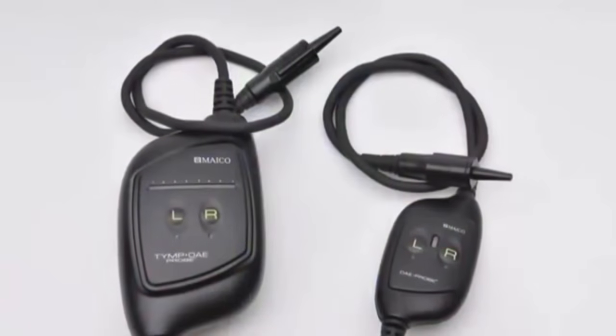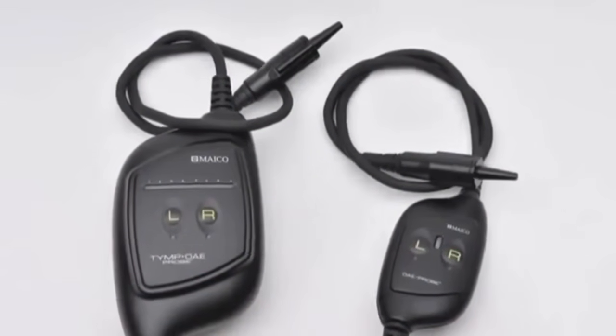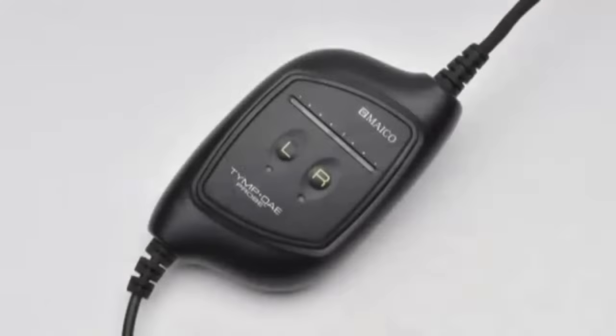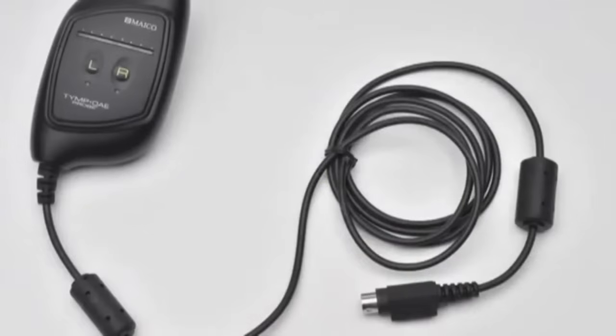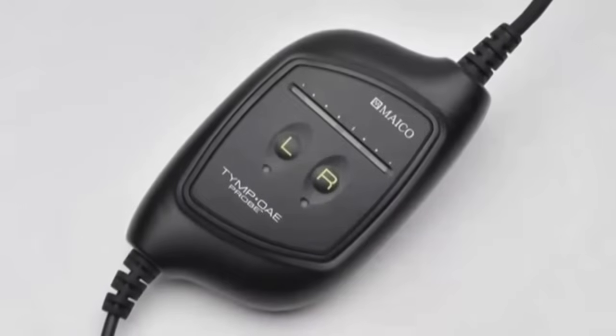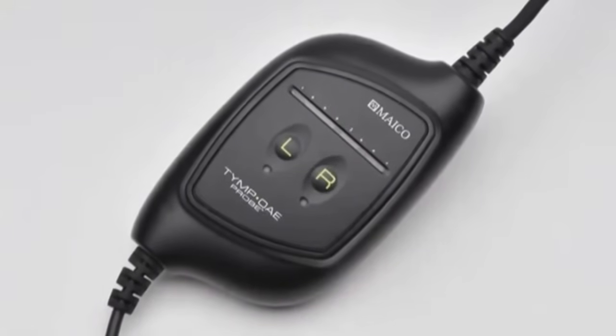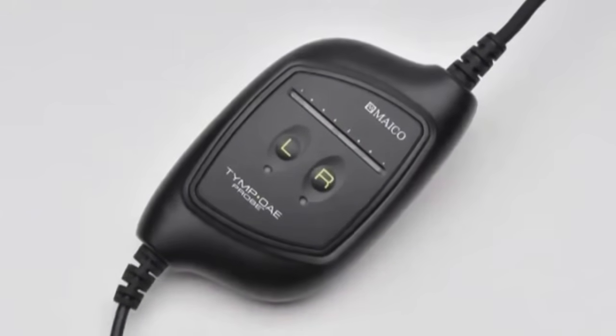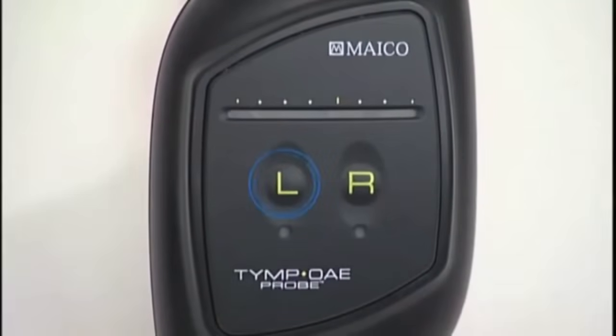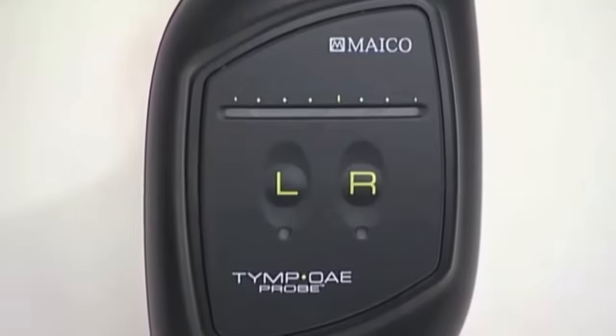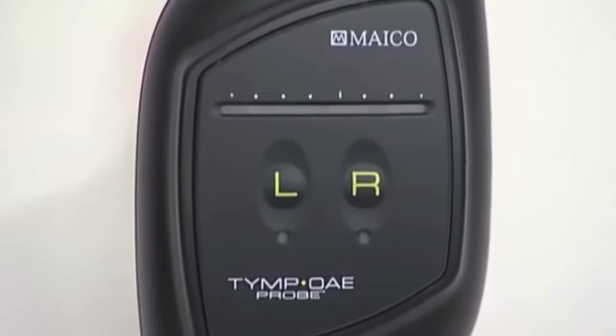All of the external probes consist of three main elements: the probe tip, the probe head, and the probe cable. The external probe enclosure features easy-to-use selector buttons. These buttons allow the user to test the left or right ear without accessing the controls on the Ero Scan Pro. This can be very helpful with many test subjects.